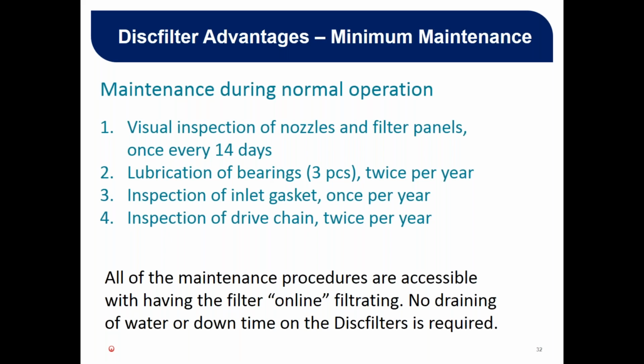Oh, and also while this maintenance is happening, like the removing of the panel and putting it back in, and the visual inspection of the nozzles, if you are not experiencing a peak abnormal condition, and your operators feel safe to do so, it is possible to continue filtering while those maintenance activities are being performed. So you actually would have no downtime. You would just put the control panel on so it does not backwash for the time that you're changing the panel, because it takes 45 seconds. So you are able to do the maintenance necessary while the unit is still online.